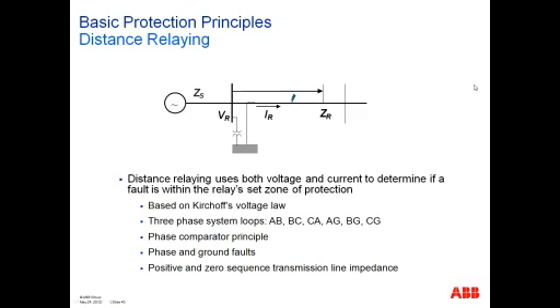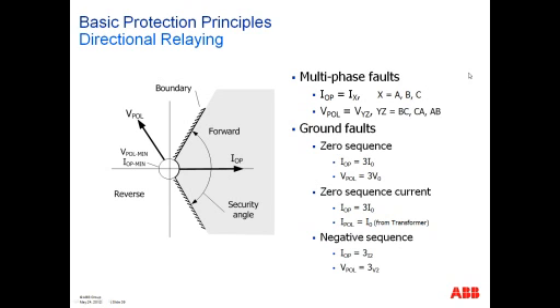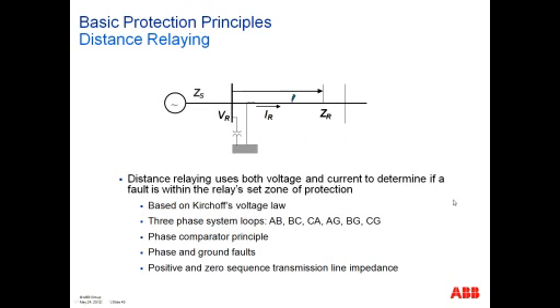Ground faults, oops, you need to go back. Ground faults, the operating quantities generally are 3I0 compared to 3V0, or it could be 3I0 compared to a polarizing current, usually taken from a transformer delta or neutral, or it could be negative sequence quantity, where the operate quantity is 3I2 and the polarizing quantity is 3V2. Okay.